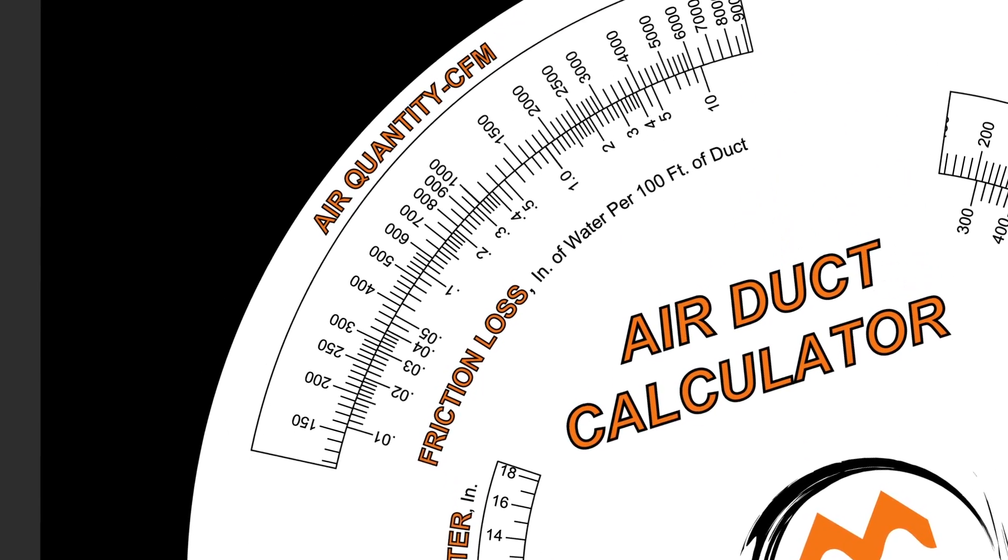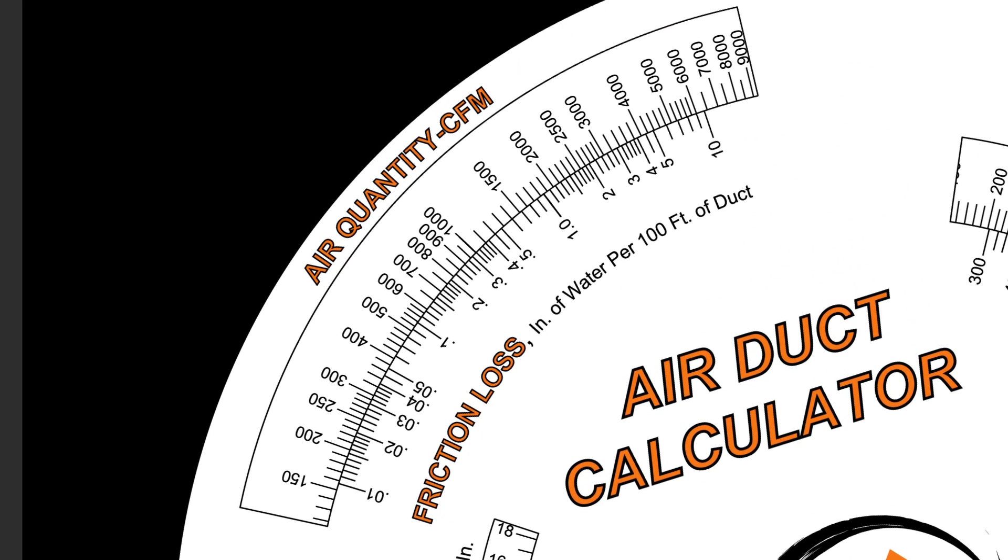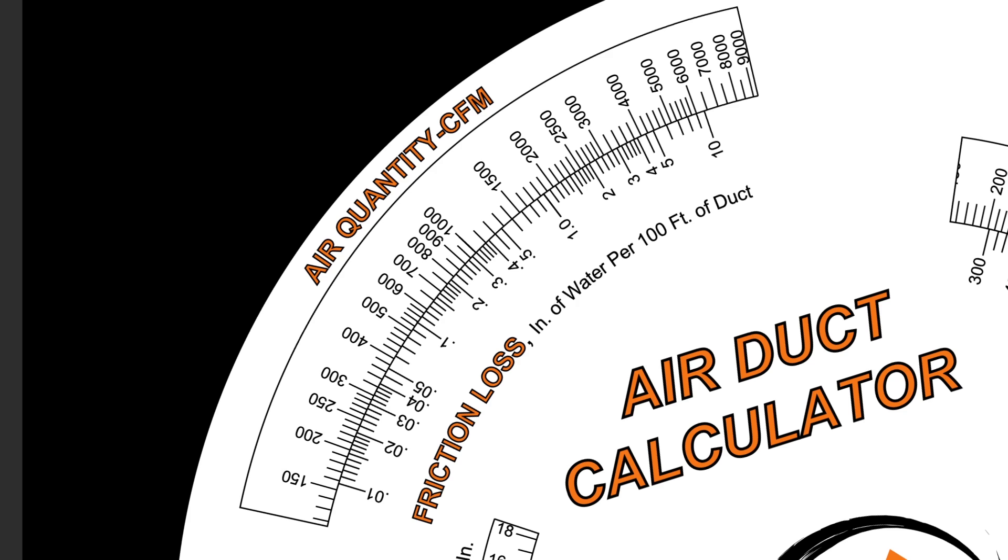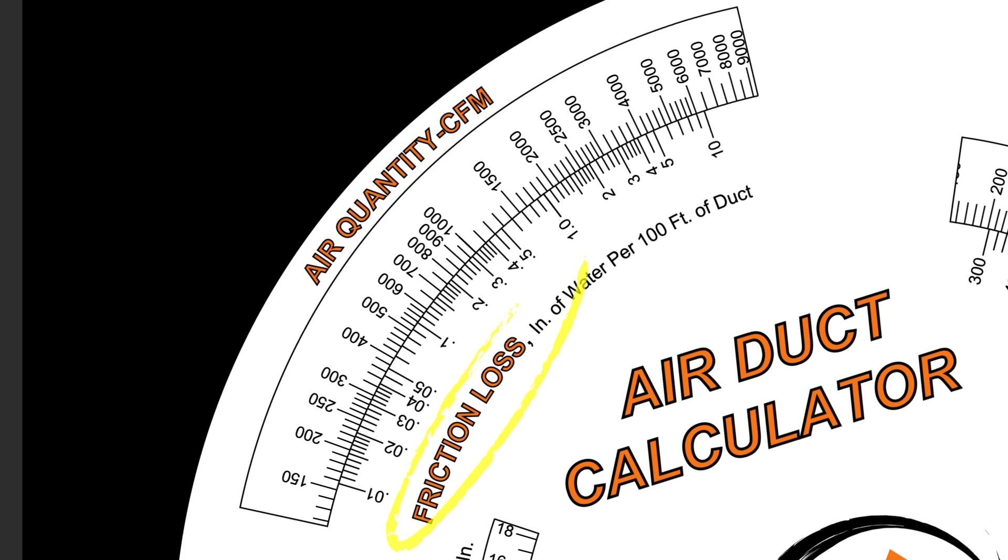Look up to the air quantity window. Here you'll see how much air can go through the duct and how much resistance the air will encounter. Inside the window is a display of your air quantity in CFM. Below that is the friction loss, also referred to as static pressure based upon 100 feet of duct.